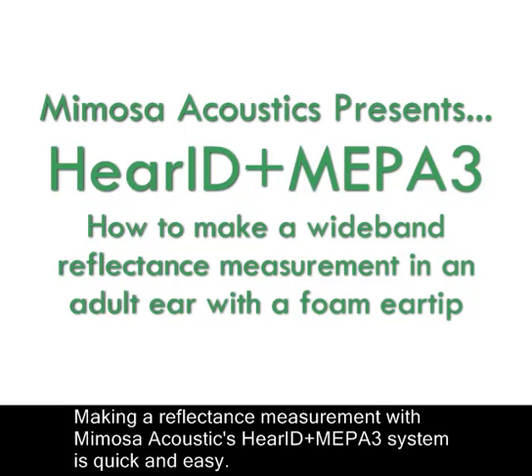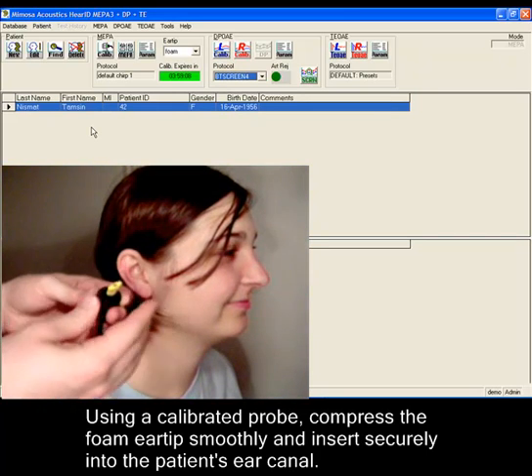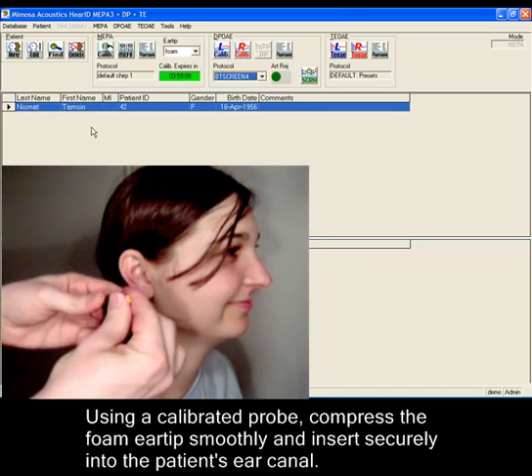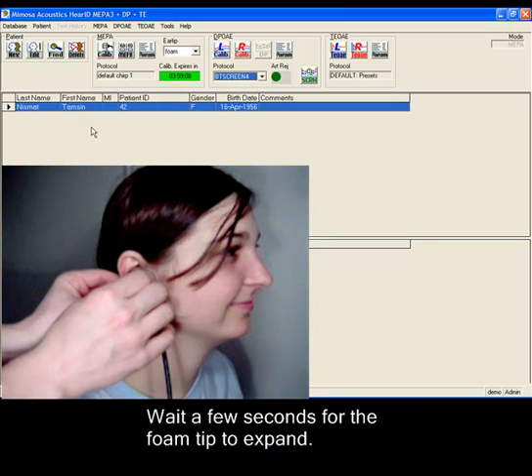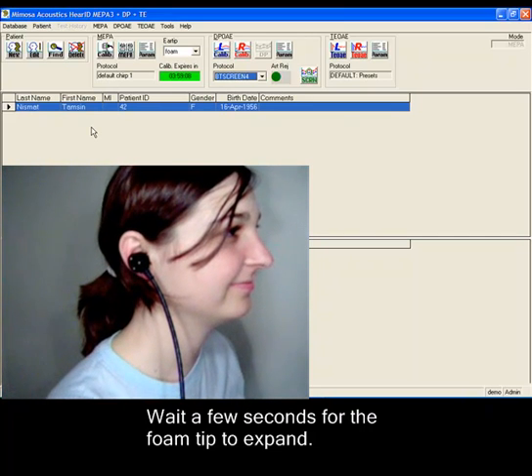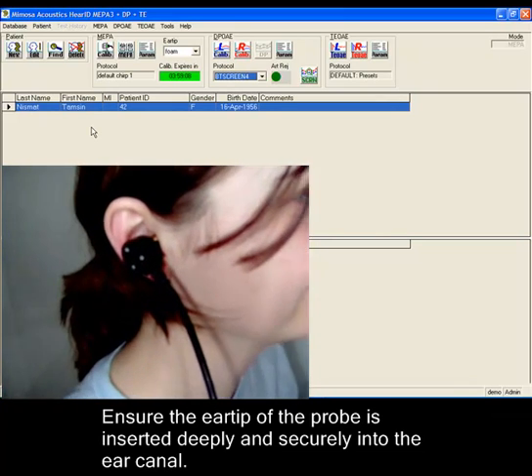Making a reflectance measurement with Mimosa Acoustics HearID+MEPA3 system is quick and easy. Using a calibrated probe, compress the foam ear tip smoothly and insert securely into the patient's ear canal. Wait a few seconds for the foam tip to expand, and ensure the ear tip of the probe is inserted deeply and securely into the ear canal.